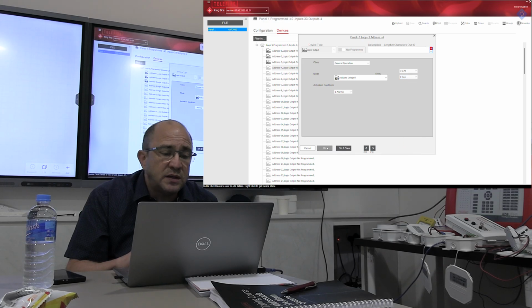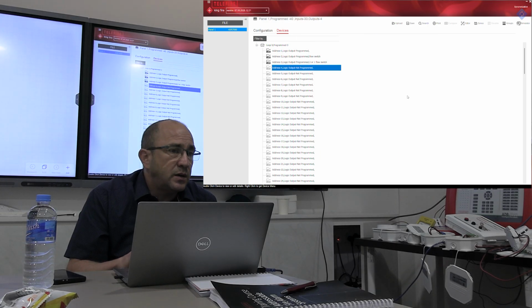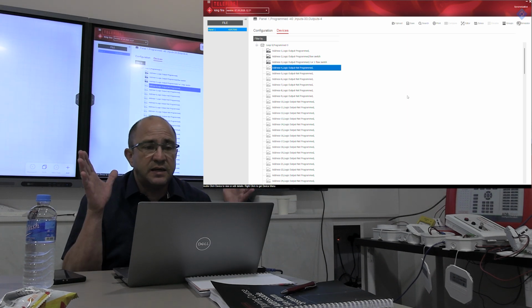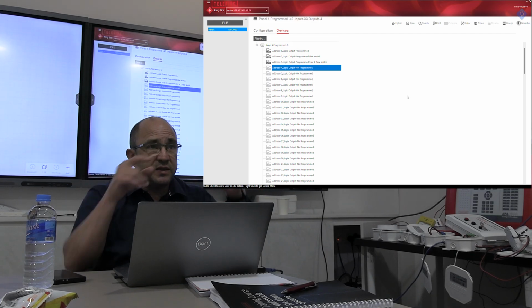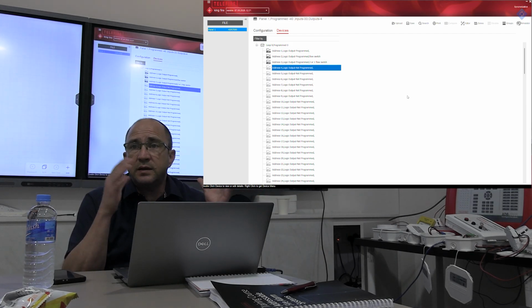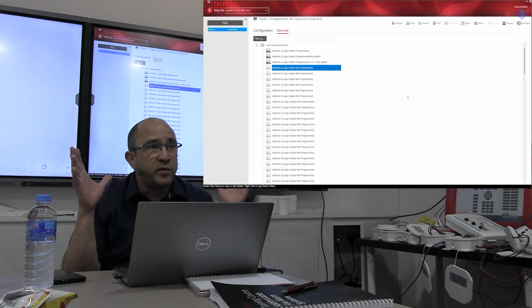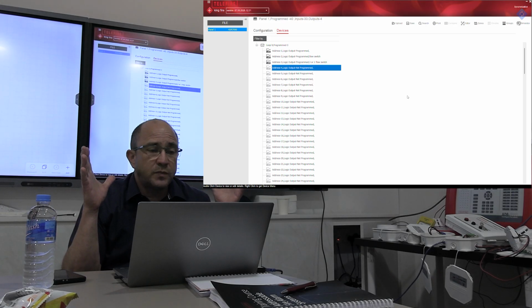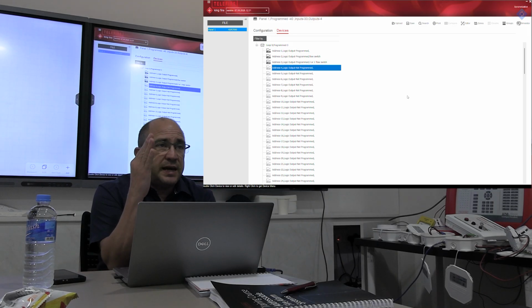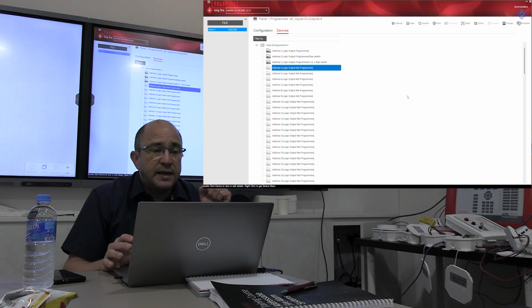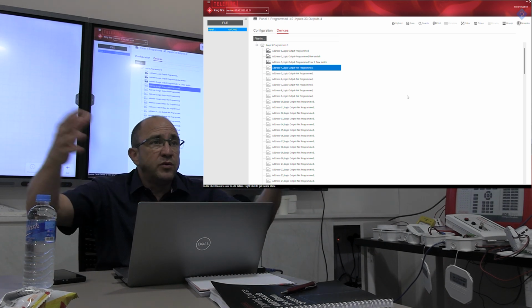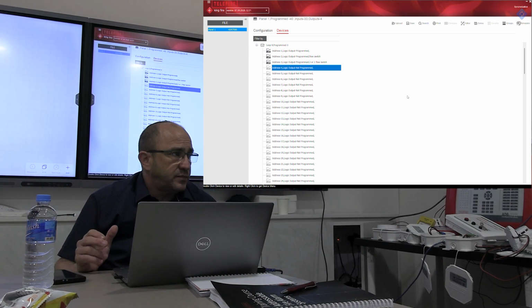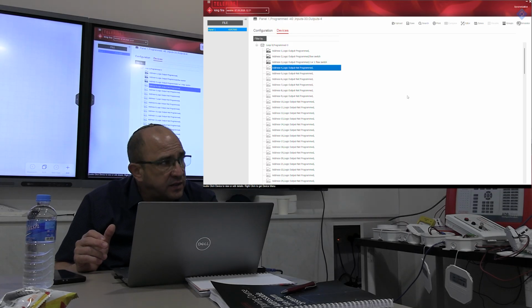The NFPA also gives you this order to follow. Let's say you have a room on the roof with an extinguishing system activated in that room, like a big electricity transformer. So you close the dampers and then you activate the extinguisher. If you're still in an alarm situation, you must give an order for the dampers to open in order to clean the room after 15 minutes. So this is activated, delayed.